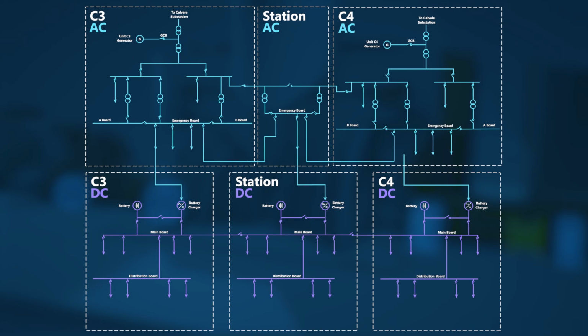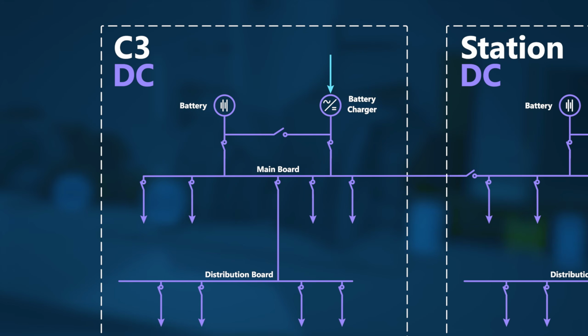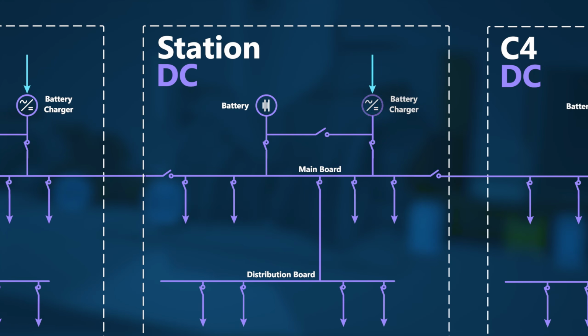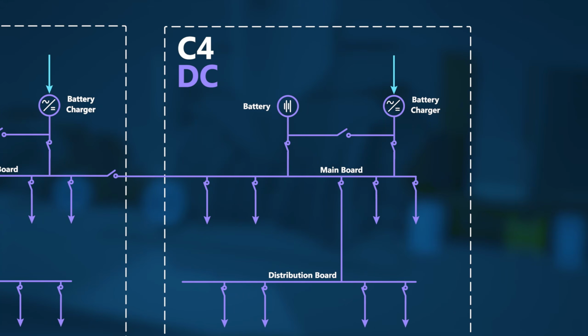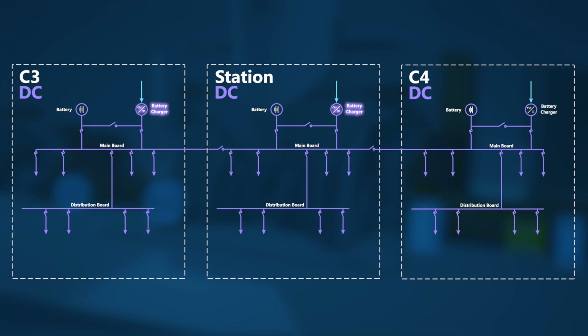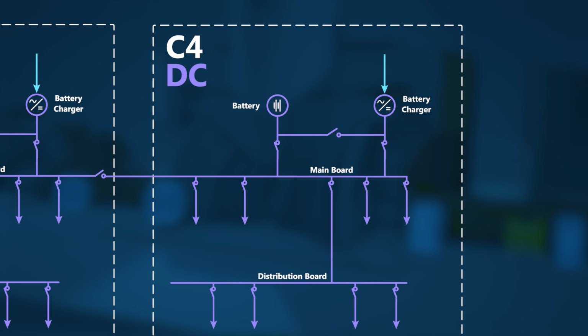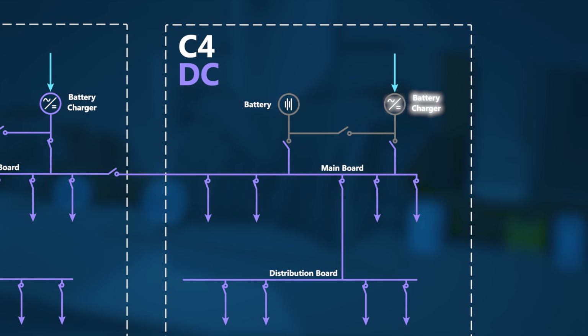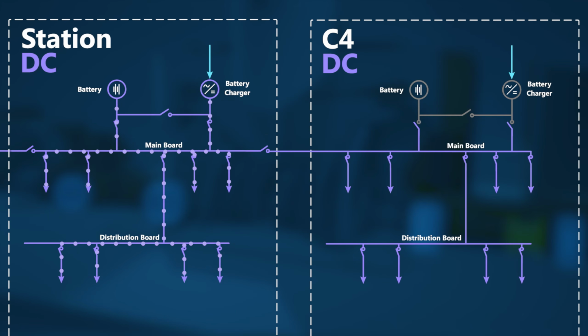In the 18 months leading up to the Callide incident, an upgrade program had been initiated to replace the battery chargers at C3, Station, and C4. The C3 and Station battery chargers were replaced and successfully brought back into service. By May of 2021, the C4 battery and battery charger had been disconnected, and the battery charger had been replaced. During this time, the C4 DC system was configured to receive power from Station through a switch called an interconnector. Now, the battery charger and battery were ready to be reconnected to C4.